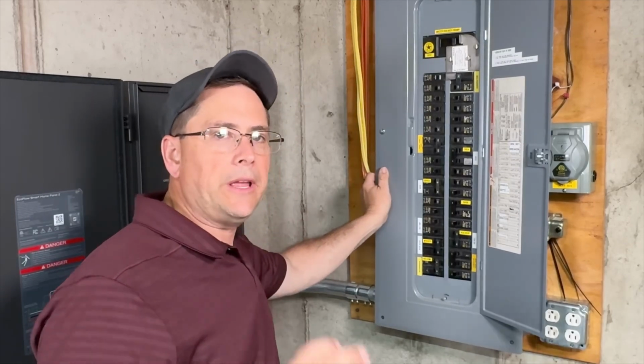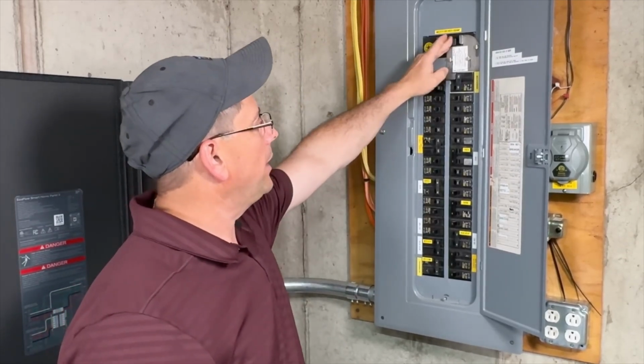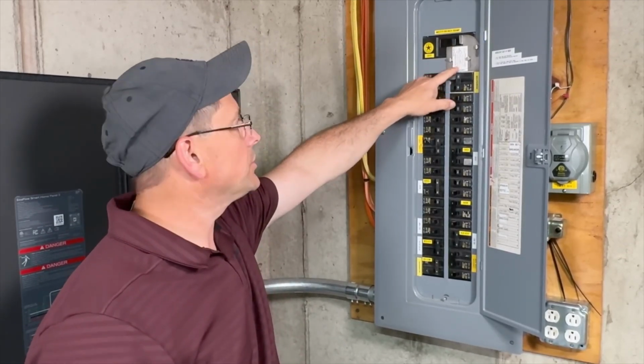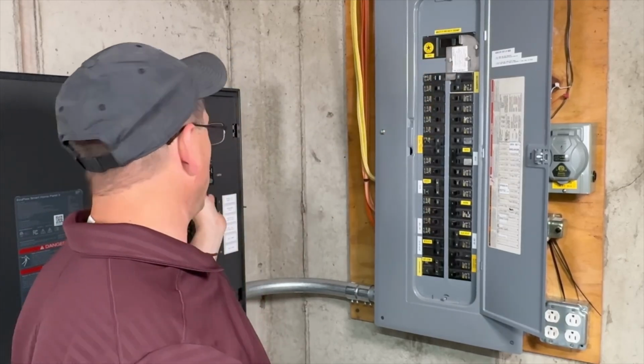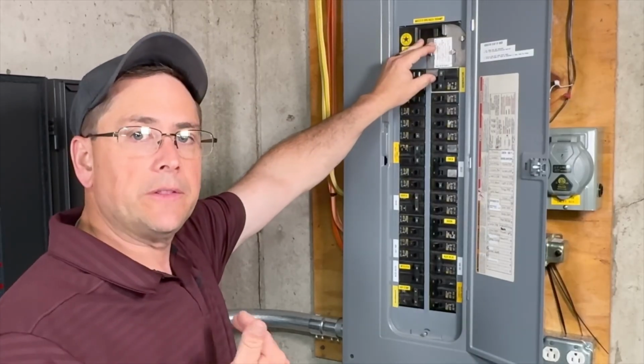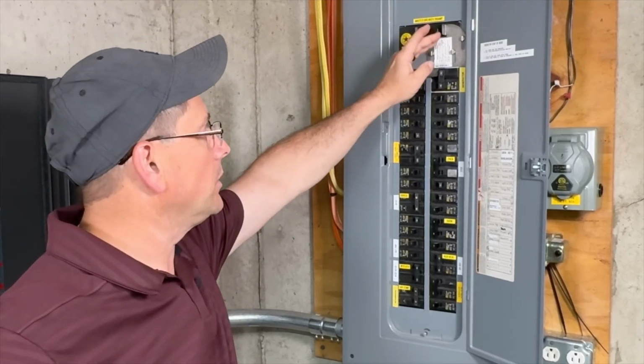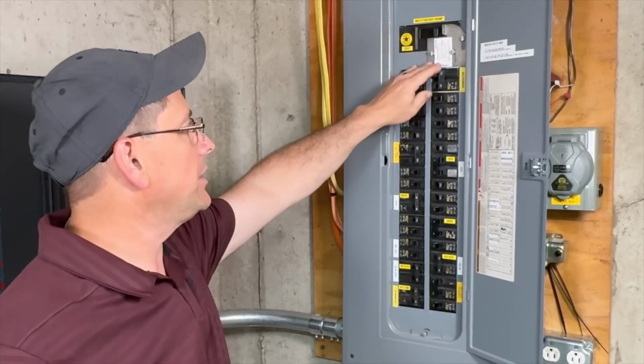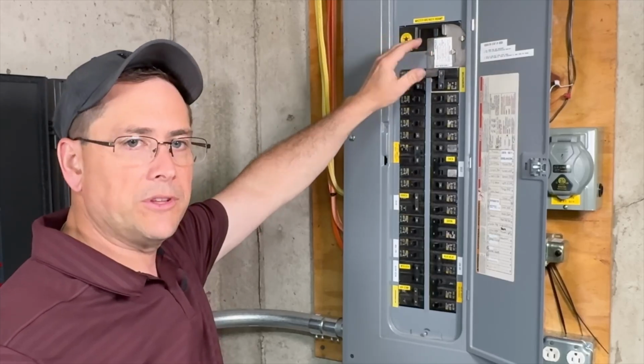What we're going to do here is mimic the power going out. This is my main breaker, and below it is my interlock switch — the same kind I had before installing the Smart Panel 2. This allowed me to hook up a gas generator or any kind of generator so I could safely control the system.